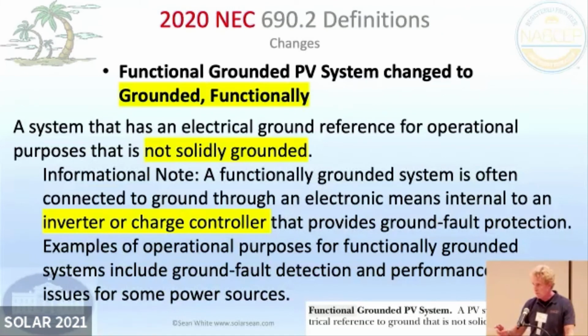And so if you measure the voltage between ground and negative or ground and positive, it's not floating around there. It's solid. It's referenced to ground. So it is functionally grounded. So anyway, we call them functionally grounded, and we have the same rules for both kinds of systems. And if you have an old, formerly known as grounded inverter, you can replace it with a functionally grounded inverter, and you don't have to change the wire types, and you don't have to change the fusing, because you only have to put fusing in one polarity. You could use USE2 wire for all the inverters now.